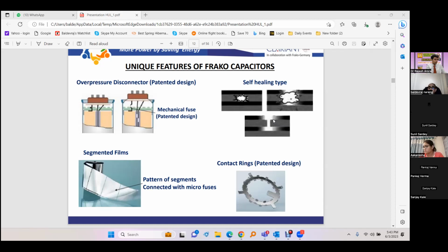So this capacitor has to take the burden, and in case the resonance is very heavy, it should isolate. It should work like a fuse. It should isolate itself so that the system is safe. The resonance is a self-correcting phenomenon. What happens is, when the capacitive and inductive reactances are equal, the resonance condition occurs. And if some capacitor blows off, this condition is broken and the resonance also goes away. So it is like a fuse.